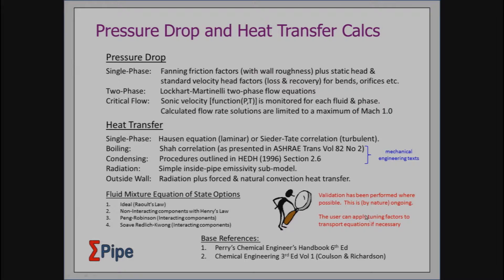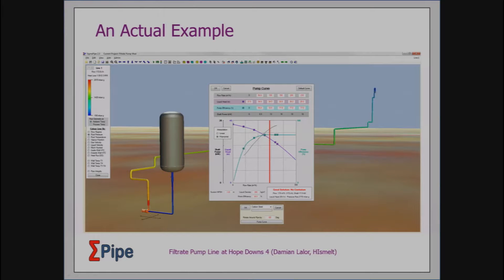It should be consistent with the sorts of things used in undergraduate teaching. This is an actual example to show how it has been used: a pump filtrate line from the Hope Downs 4 mine in the northern part of Western Australia. There was a problem with this circuit, and the question was: is it performing according to design? They had all the pump curve parameters and the line layout, and the question was whether something was wrong with the line or something else. It was set up and simulated as a tool in a forensic process investigation — something plant engineers often have to do because real plants keep doing things they're not supposed to.